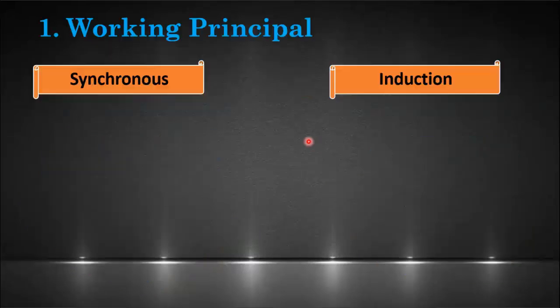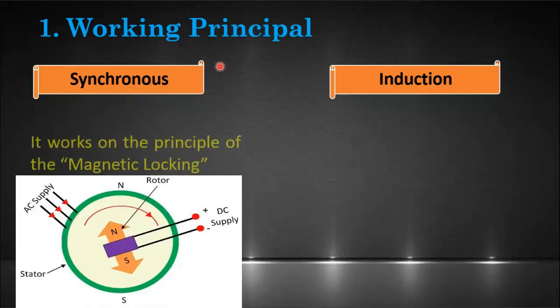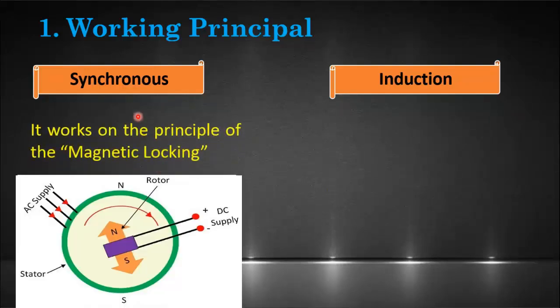The first difference is based on the working principle. The synchronous motor works on the principle of magnetic locking. There are two magnetic fields in the synchronous motor — one on the stator and the other on the rotor — and the rotor field locks with the magnetic field of the stator, causing the rotor to rotate at synchronous speed.